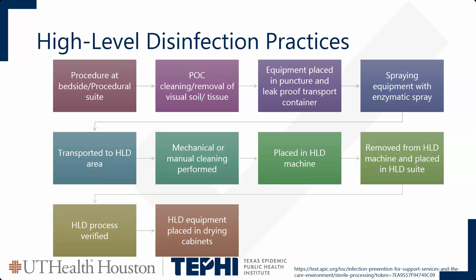And in case something came back, say the device got exposed to an MDRO and it wasn't cleaned properly, you can trace it back to the patient, let the patient know this event has happened, and tell them that you'll be tracking and following them outside of the facility to ensure that they don't have one of these types of infections. So then once the cycle is done on the reprocessor, the device is physically removed and placed in the drying cabinets at the right pressure, hooked up to the airflow and freely suspended. That means not touching the bottom of the cabinet, the side, or another scope.